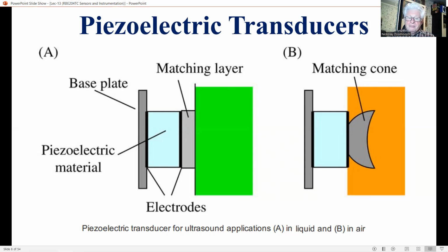Irrespective of the application, the transfer of sound energy from transducer to medium or vice versa is crucial for the S/N ratio of the measurement signal. As explained today, the transfer is governed by the acoustic impedance of the materials involved. Obviously, since a piezoelectric ceramic material has a high acoustic impedance compared to air, the efficiency of power transfer to air is extremely poor. Also, for every liquid or solid medium, power loss can be considerable too.